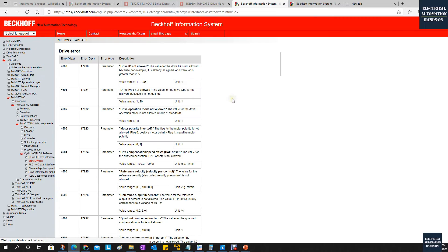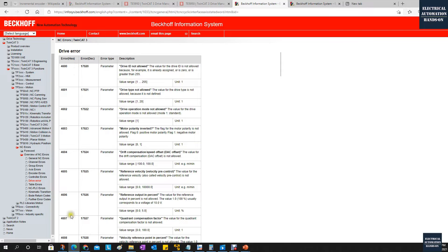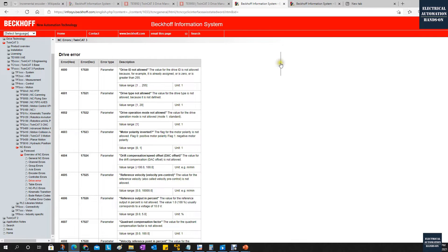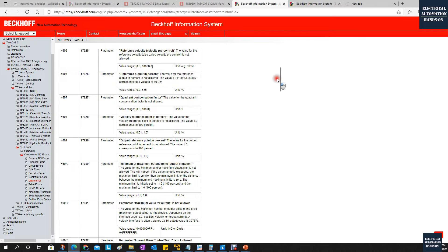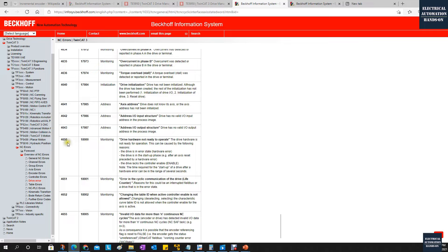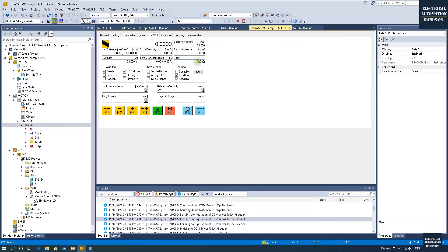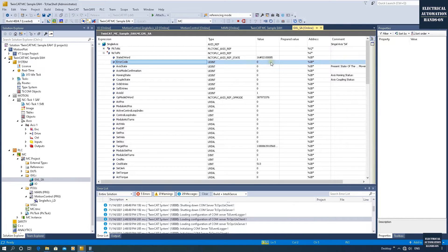Searching for 4650 in the Beckhoff Information System gives us a Drive Error. From these two lines we can see the hex and the decimal. Scrolling down to find the detail code, 4650 in hex corresponds to 18000 in decimal — this is a 'monitor fault', meaning the drive hardware is not ready to operate. For example, if your drive has safety disabled, or if your torque is limited to zero by accident, the drive cannot turn on and run. So the drive will show error 4650, and the error code 18000 will show both in the NC to PLC section and in the axis error code.